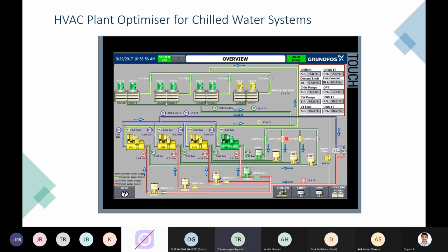Okay, so what we had touched upon is more of individual water application. What we also have in the market is automation for your chilled water system requirement. Like in a power plant, obviously there will be a chilled water demand, and based upon the demand, the chiller, the pumps, or the cooling tower is going to operate. So this kind of plant optimizer will help you take the data of your chiller, cooling tower, and pumps, and try to run all the systems efficiently, so that your building comfort is met, and also your overall energy consumption is reduced. So this is also a new avenue on the chilled water system approach, where a lot of saving potential is available.